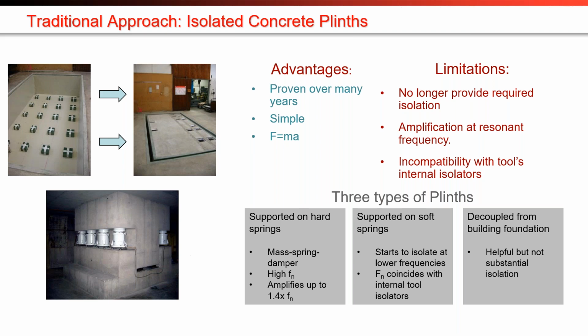So the advantage of this type of approach is that it's time proven. It's what people have done for a long time. It's simple, relying on the simple physics of F equals ma, right? The larger the mass, the more force it's going to take to accelerate it to a given vibration level. So it's simple and reliable for a long time, but it's becoming increasingly obsolete for a few reasons.